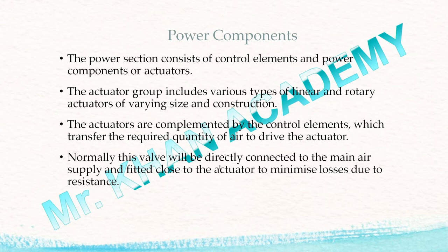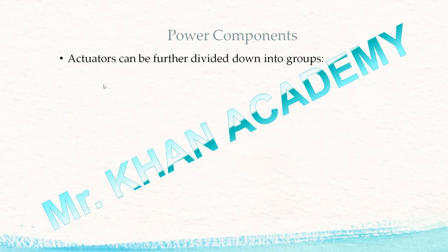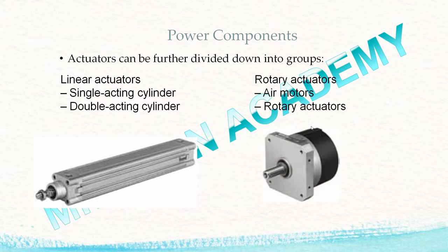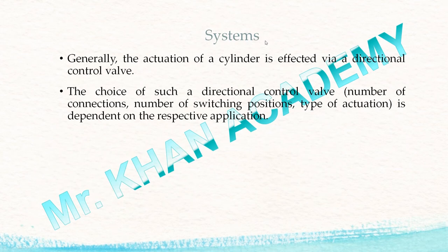Normally this valve will be directly connected to the main air supply and fitted close to the actuator to minimize losses due to resistance. The power component is divided into the following groups: linear actuators — that is single acting cylinder or double acting cylinder — and rotary actuators — that is air motor and rotary actuator. If you want linear motion, we use the linear actuator; if you want rotary motion, we use the air motor and rotary actuators.